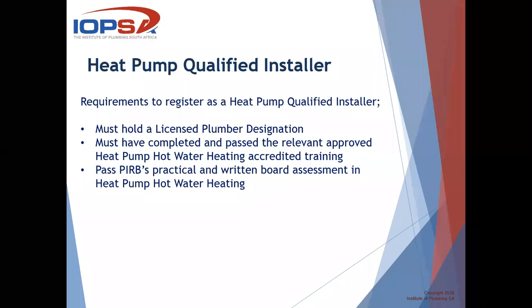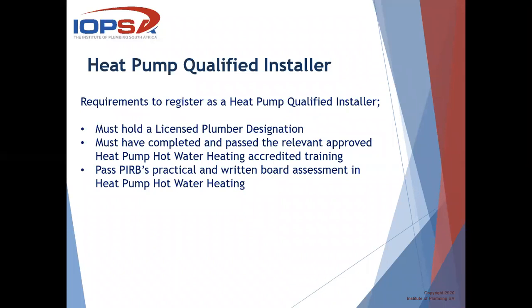So similar to the solar qualification, this is a specialization. Once again, there are specific installation methods and components connected to the heat pump. So if a geyser is in any way connected to a heat pump, then it is classified as a heat pump installation for the purposes of issuing the COC.